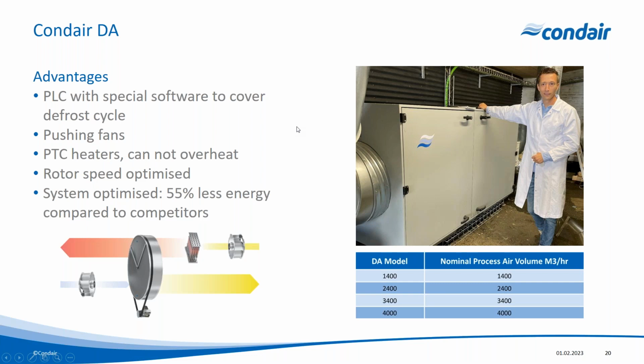Now, the great thing about this product is that we've got a PLC, a programmable logic controller with software that's going to control any defrost cycles that have to happen inside the unit. And we've got fans as well that we can control and optimize the speed of. So we can optimize the speed of both the fans, and we can optimize the level of heat, and we can optimize the rotation speed of the rotor, to give us the most efficient form of dehumidification that's optimized specifically for the cold store or the chill store in question. That means that an optimized system typically will use 55% less energy compared to just a standard unit that you're going to drop into your freezer store and dehumidify.